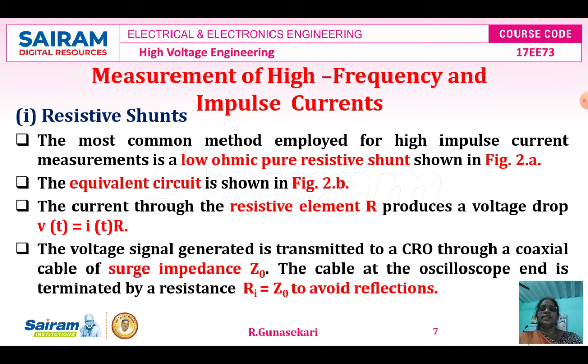The first method is the resistive shunt. The most common method employed for high impulse current measurement is a low ohmic resistive shunt, shown in figure 2A. The equivalent circuit is shown in figure 2B. The current through the resistive element R produces a voltage drop: V(t) = I(t) × R. This is the general principle, the same V = IR logic applied in the time domain.